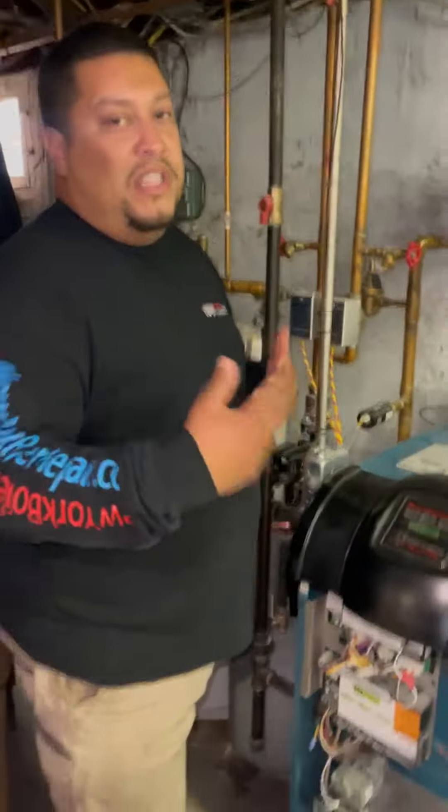It's a little hard to see — it's on the back. You follow this wire and there's a spill switch right in the back. You guys can see it right there. And it has a manual reset.